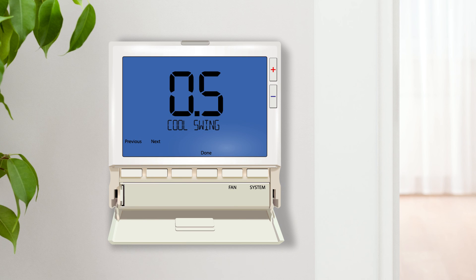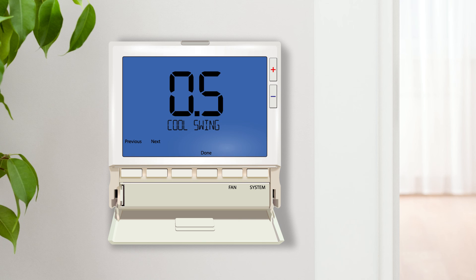Cooling swing, often called cycle rate, differential or anticipation, is an adjustable value that determines how frequently the cooling system will cycle on and off. The smaller the swing setting, the more frequently the equipment will cycle. This will improve the comfort but will put more wear and tear on the equipment. A larger swing setting will increase the lifespan of the equipment but will cause a larger temperature fluctuation.